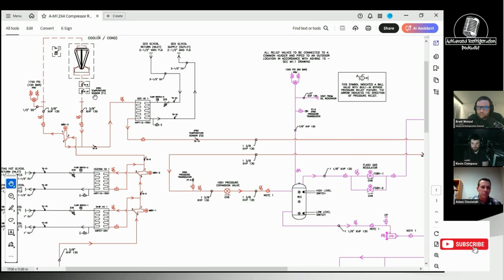Because if you think of it this way, if the fan set point's the same, let's say you're running a 60-degree drop leg, okay? So you've got 60-degree liquid. Now you raise the set points, you still have 60-degree liquid coming in. So your enthalpy difference in your receiver doesn't really change. So your refrigeration effect doesn't change, your flash gas doesn't change a whole lot. What it does do is just add additional heat of compression, just motor heat. So it does increase the discharge temperature.